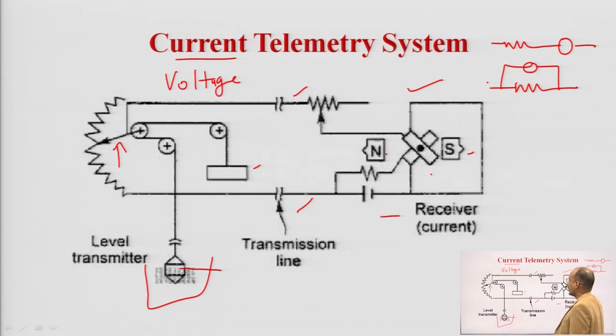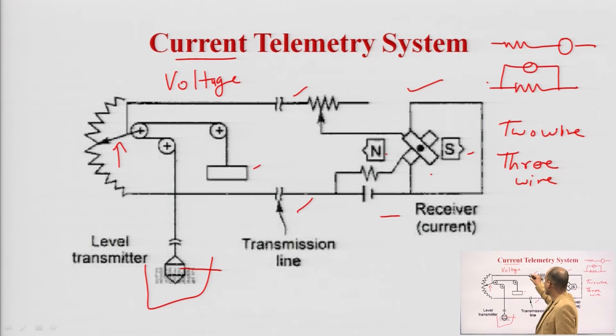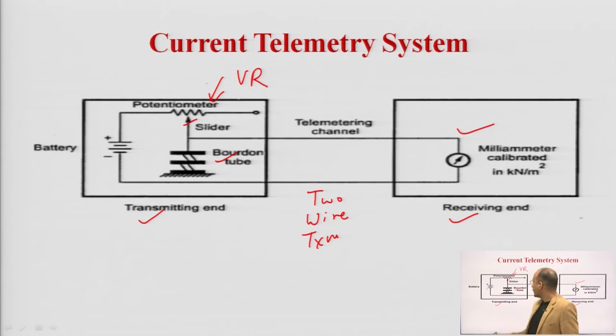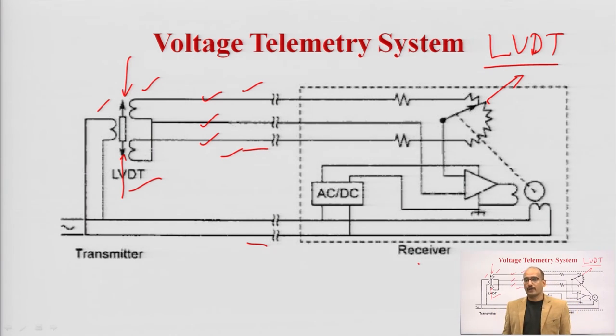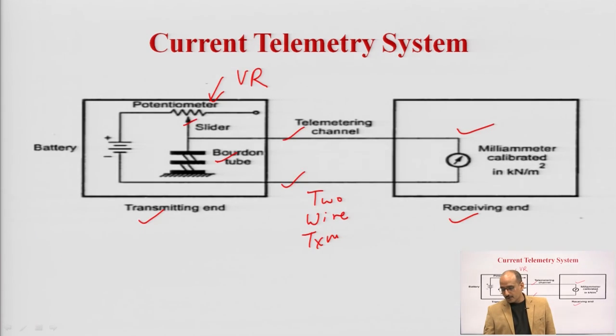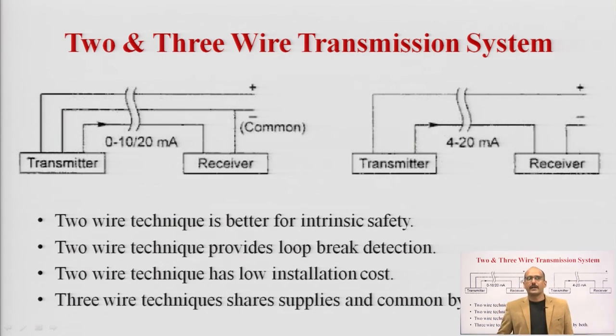Another difference is whether you use two-wire or three-wire transmission. In this diagram, two-wire transmission is used. In the previous LVDT diagram, three wires were used. The two-wire and three-wire transmission systems are arranged as per the current value. For 0 to 10–20 milliampere range, three-wire transmission is used, while for two-wire, only 4 to 20 milliamperes is applied. This topic of two-wire and three-wire transmission is very important and frequently appears in AKTU examination questions, whether worth 5 marks or 2 marks.